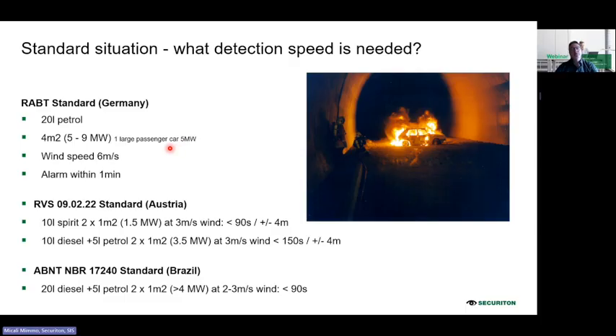The only thing is that the norm does this test with quite a high speed. We are talking about 6 meters per second wind speed. And the norm says that this kind of test must be detected within 1 minute. So the system must be really fast to detect in less than 60 seconds under such conditions, even though we have quite a big energy during this fire test. You have to consider that the wind speed is also a very important factor. That means the temperature will increase, but will not increase so fast due to the wind speed.